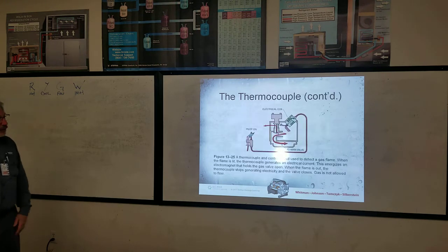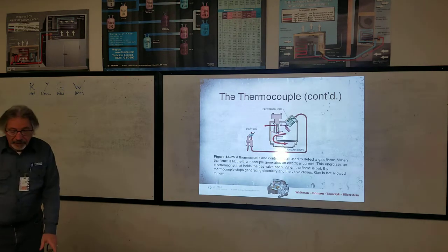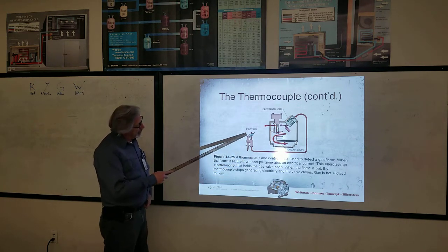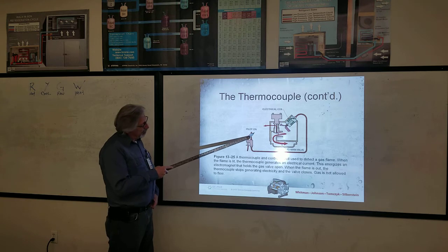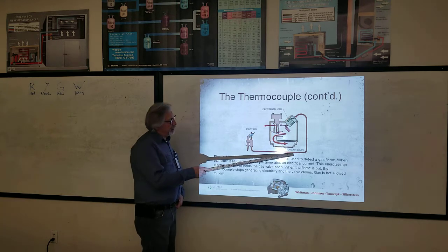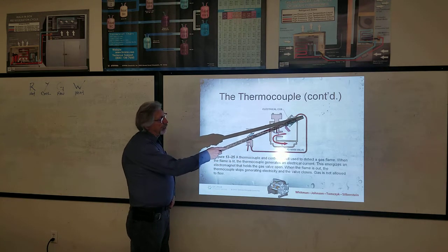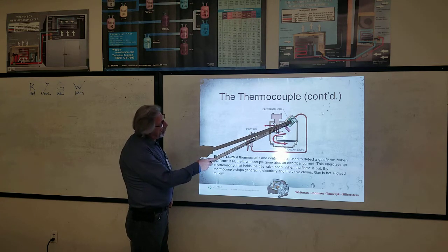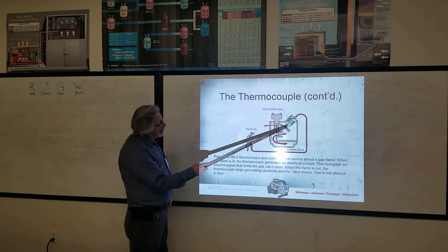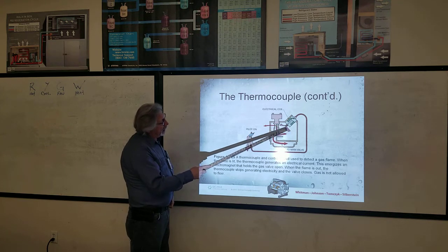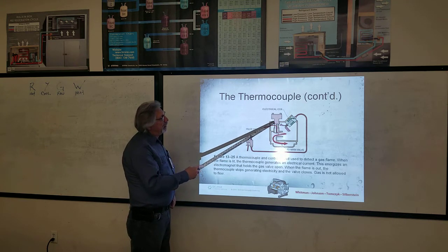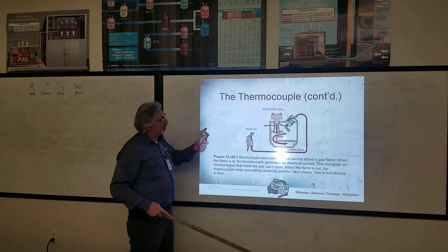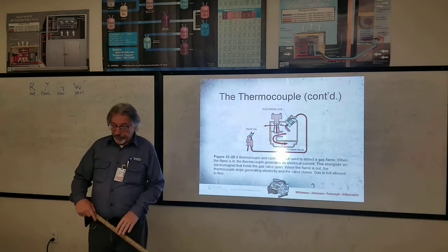Okay, so here is the action photo. This is what the thermocouple does. As the pilot heats it up, like in the cartoon, it sends a little signal, about 20, 30 millivolts, and it holds open this little coil. And this little coil has a little latch on it, and it allows the main gas to open and close. Now, if it was cold, this latch would hold that valve so it couldn't open.